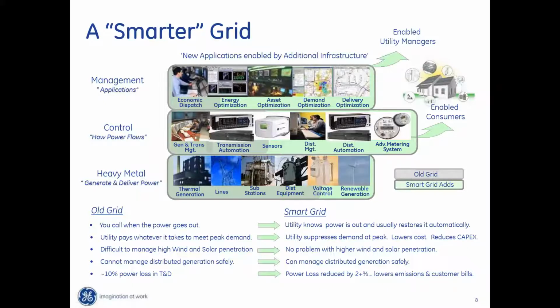For instance, on the bottom there, voltage control. Voltage is directly proportional to load. So if it's a summer peaking utility and it's a hot summer day and utility is approaching its previous peak, we will lower the secondary voltage, which will lower the load, okay? Now, we also do reactive power control, right? We want to reduce the losses on the system. We call that VAR control, right?